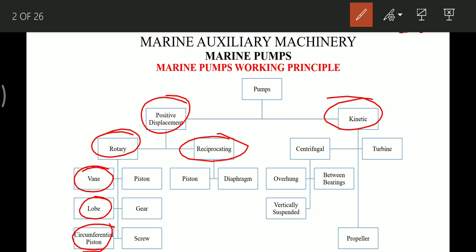Circumferential piston pumps are used in winches or windlass. Then we have rotary piston pumps, which are used in steering gear where variable delivery is required using a swash plate. Then gear pumps, which are used for lube oil systems, and screw pumps, which are used as supply and booster pumps for fuel oil.